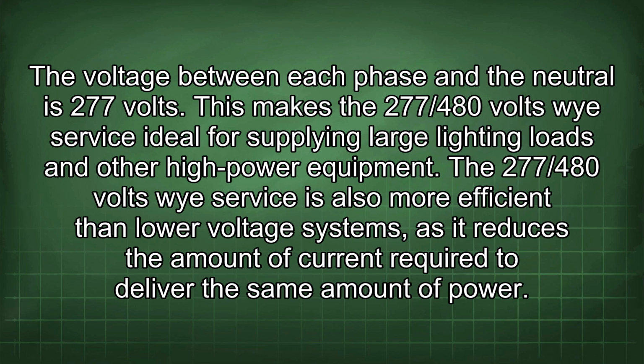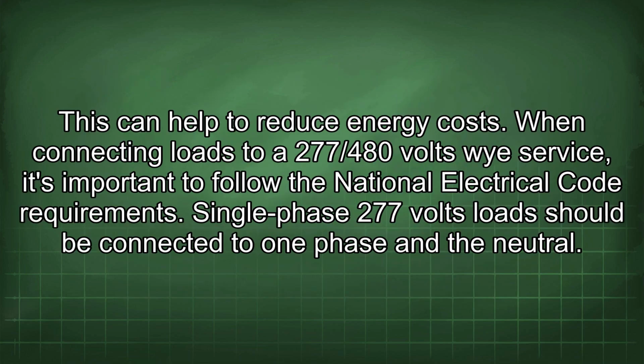This makes the 277/480 volts Y service ideal for supplying large lighting loads and other high-power equipment. The 277/480 volts Y service is also more efficient than low-voltage systems, as it reduces the amount of current required to deliver the same amount of power. This can help to reduce energy costs.